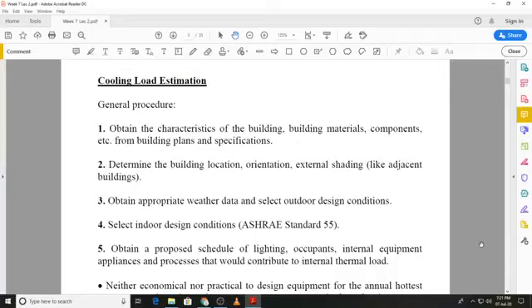When we say schedule of lighting, we will need to know how much wattage is installed, when do the lights come on, when are they switched off. Similarly, how many people are using that building, when do they come into the building, for how long do they stay inside the building. And similarly for the equipment, what are the types of equipment being used, what is their power consumption, what are the times over which those equipments are used, or any other process that causes a thermal load inside the building.